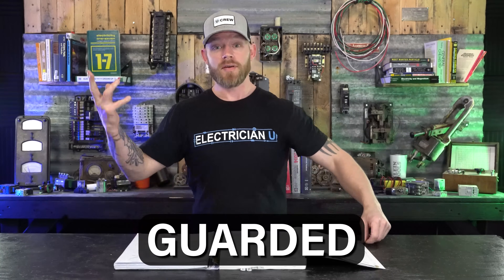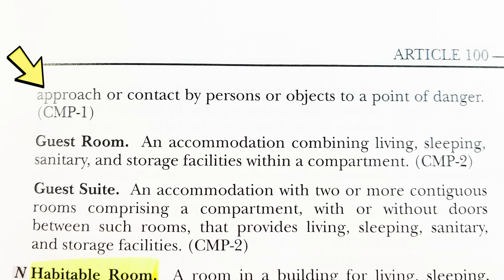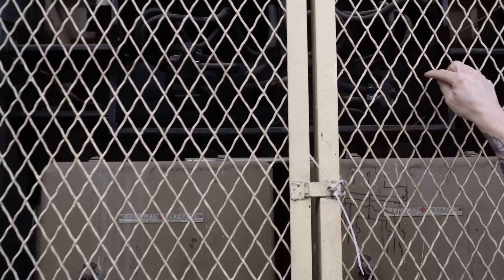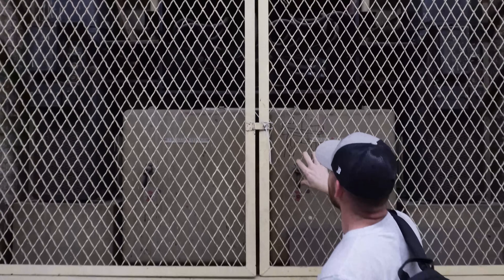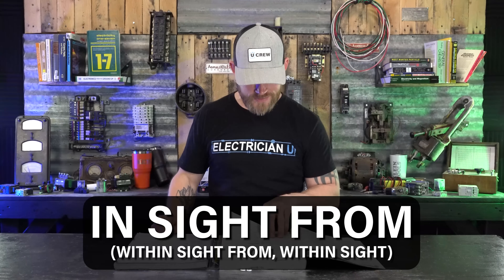Next we have 'guarded.' By code, guarded means covered, shielded, fenced, enclosed, or otherwise protected by means of suitable covers, casings, barriers, rails, screens, mats, or platforms to remove the likelihood of approach or contact by persons or objects to a point of danger. It's a similar concept to enclosing, but guarding is less fully preventative — something is being guarded rather than fully closed off.